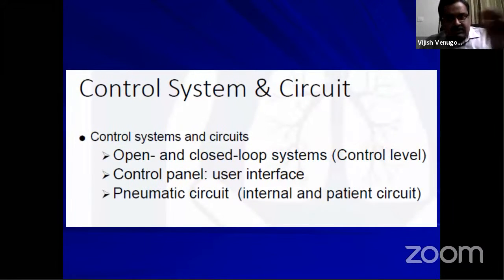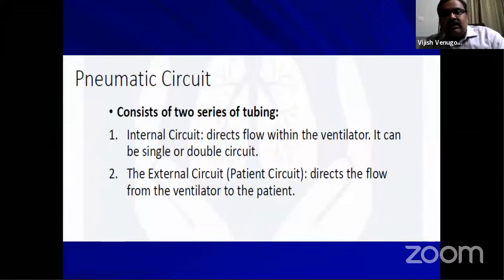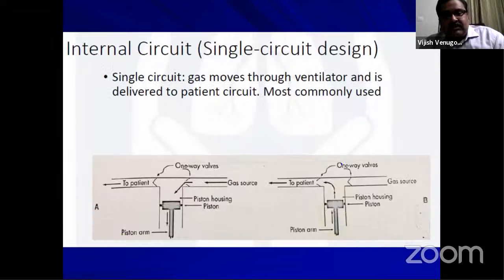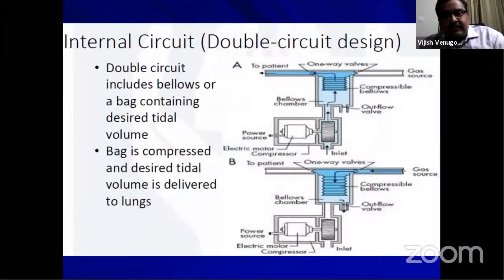Now coming to the control system and circuit, you have a pneumatic circuit as well as electrical components. If you look at the pneumatic circuit, there are two types. There is a circuit within the ventilator, called the internal circuit. And there is a circuit which is outside, that is the patient circuit, your ventilator tubings, which you connect to the patient. So the internal circuit could be a single circuit design, where there is only an inhalational valve which opens and the piston pushes air through to the patient, and this is the most commonly used.